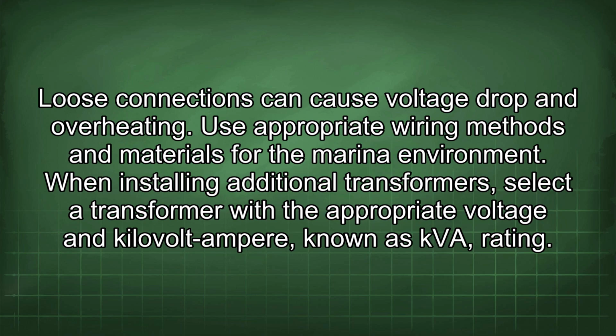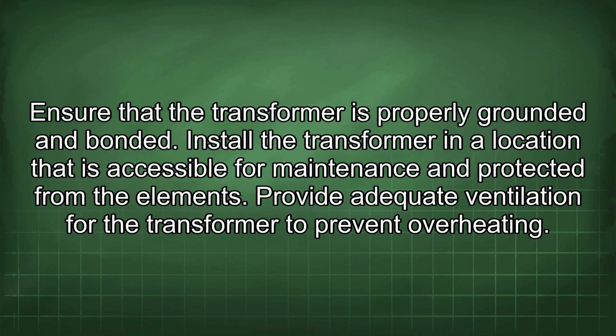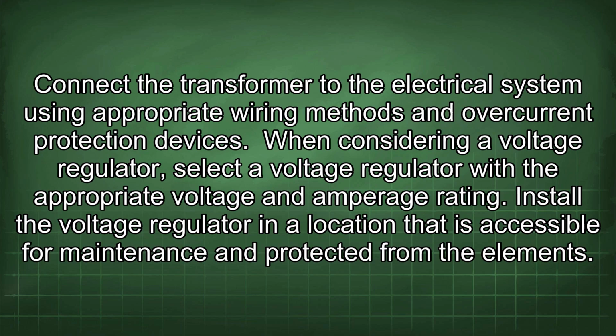When installing additional transformers, select a transformer with the appropriate voltage and kilovolt ampere, known as kVA, rating. Ensure that the transformer is properly grounded and bonded. Install the transformer in a location that is accessible for maintenance and protected from the elements. Provide adequate ventilation for the transformer to prevent overheating. Connect the transformer to the electrical system using appropriate wiring methods and overcurrent protection devices.